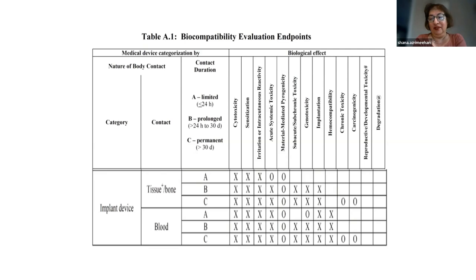Another important component is what tissues are exposed. If you have a device that's going to be in contact with circulating blood, then you're going to have a greater amount of testing to make sure that this device is safe. There's nothing leaching out that will change your systemic exposure. And so those are very important. Like skin devices require much less testing as listed above here.